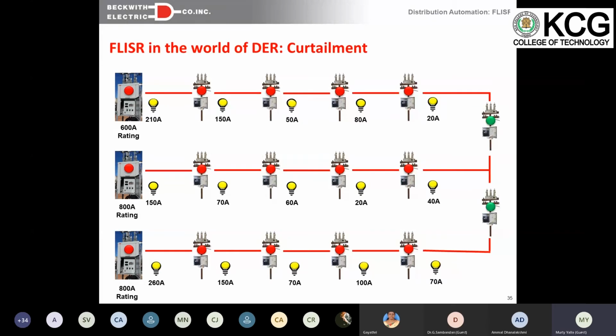So in order to improve the reliability of the electric power system, especially in the United States, you have feeds coming into the houses from multiple places. So you've got 3 substations shown here, connected to all these loads, and towards the end there's a link between these. Suppose if you have a fault, that section can be isolated, and then you can feed the power from the opposite end. Things like that.